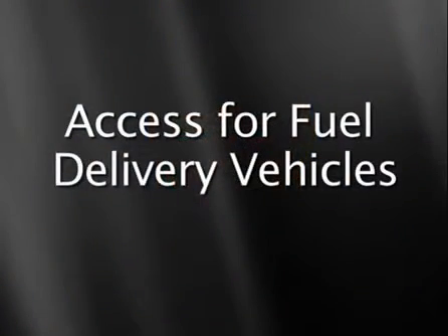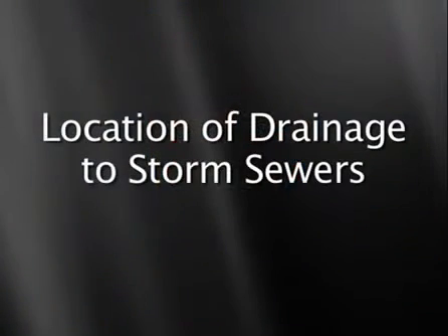An above-ground tank at grade, adjacent to a building, will look as good as a tank can look. For that reason, they are typically enclosed by architectural walls or fences. The tank needs to be located so that a fuel delivery truck can drive adjacent to it for filling, although remote fill stations can be used if this is a problem. The tank and fuel delivery area is designed to be separated from the storm drain inlets. This is to allow any leaks or spills to be cleaned up before flow to stormwater systems.